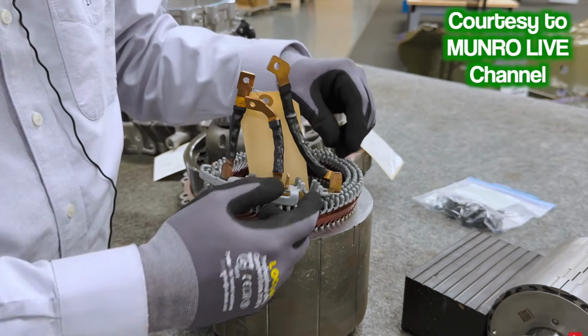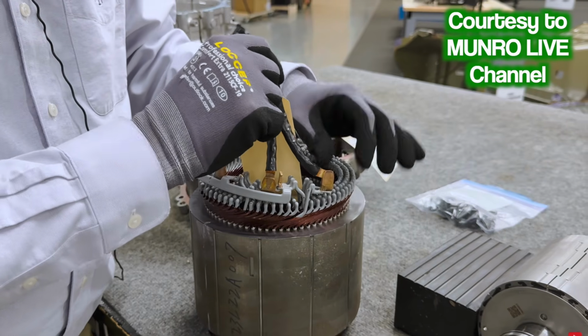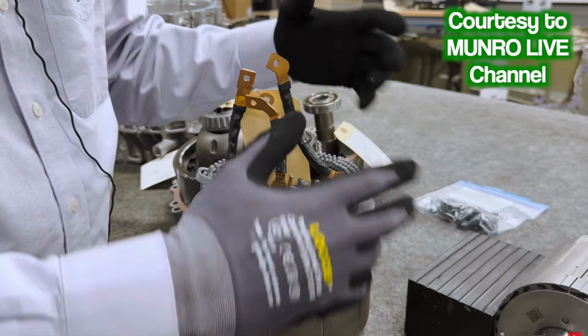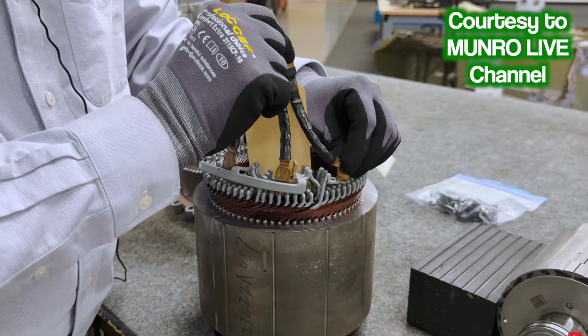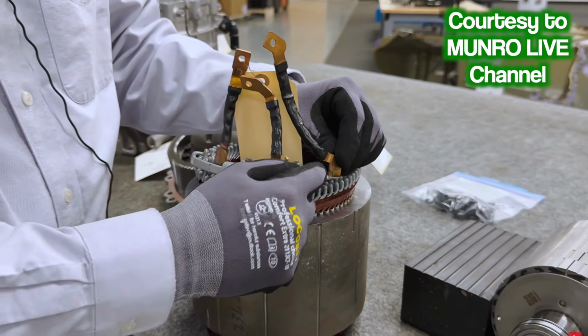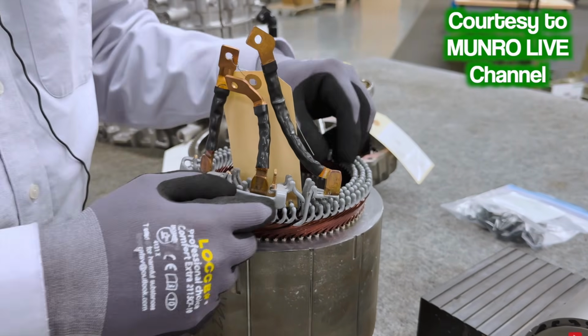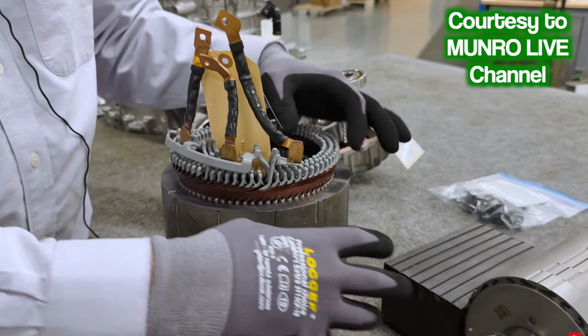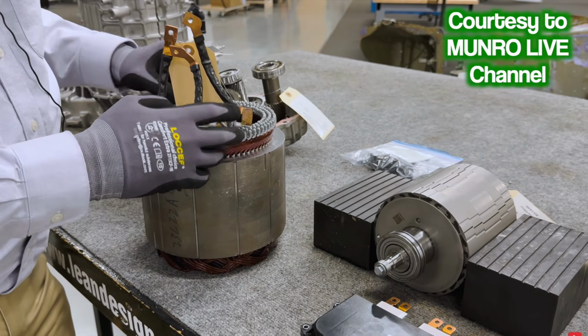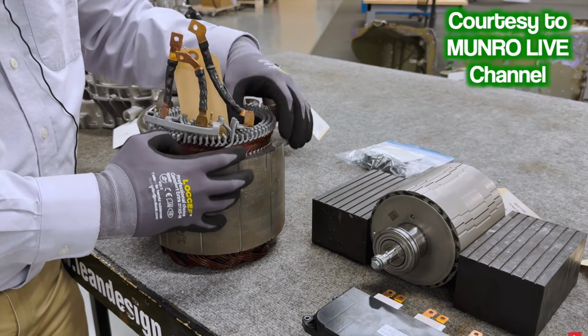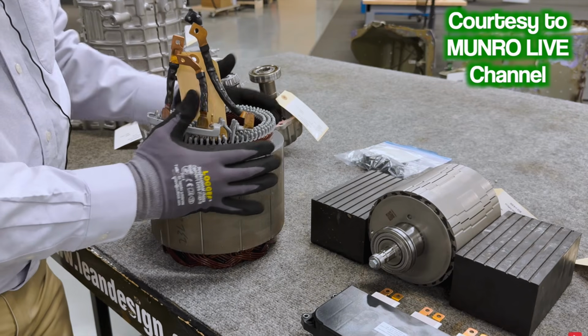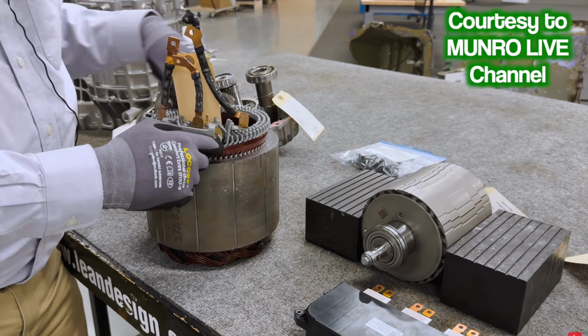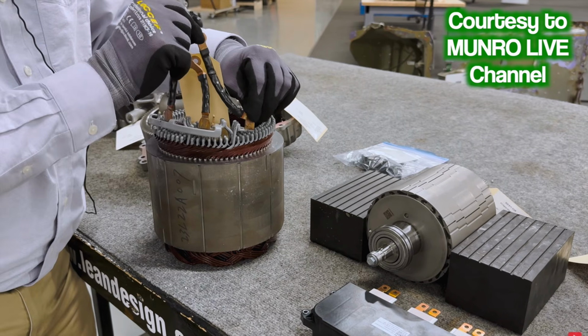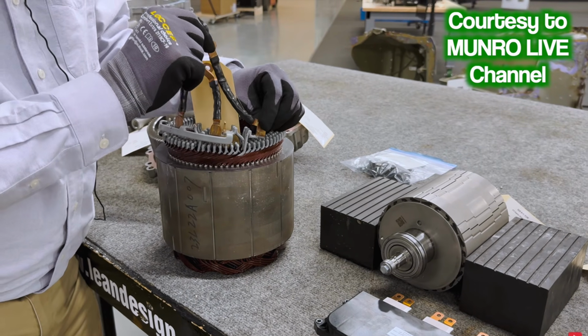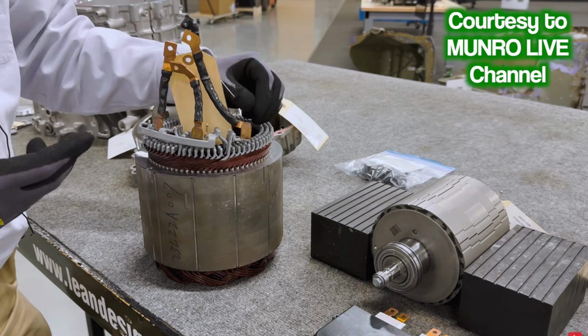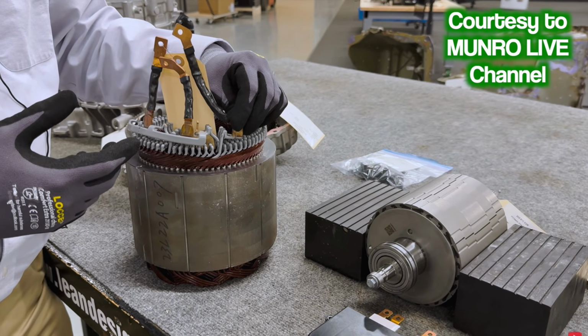In addition, just the weight of this, as you vibrate it going over the road, every bump gives a little vibration that also puts stress on that joint. Then there's further vibration: the rotor spinning moves these wires, and the magnetic fields are so strong they actually distort this housing and produce a high frequency vibration that again moves this joint. Between all of those forces, this joint ends up seeing quite a lot of vibration.